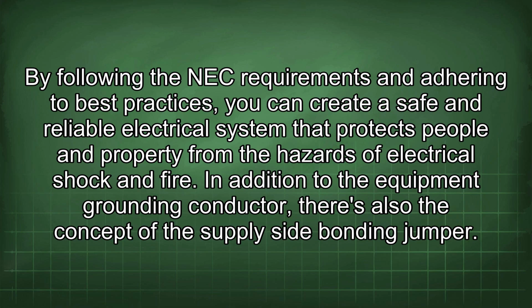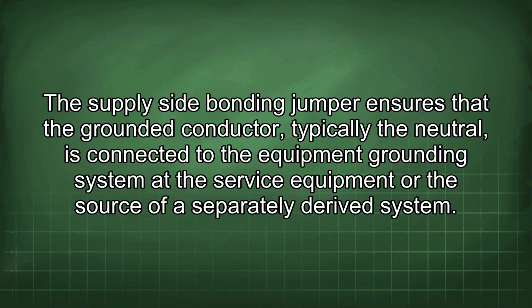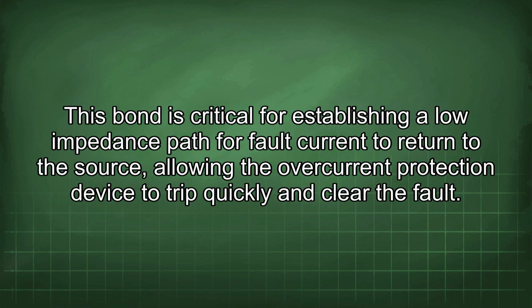In addition to the equipment grounding conductor, there's also the concept of the supply-side bonding jumper. The supply-side bonding jumper ensures that the grounded conductor, typically the neutral, is connected to the equipment grounding system at the service equipment or the source of a separately derived system. This bond is critical for establishing a low impedance path for fault current to return to the source, allowing the overcurrent protection device to trip quickly and clear the fault.